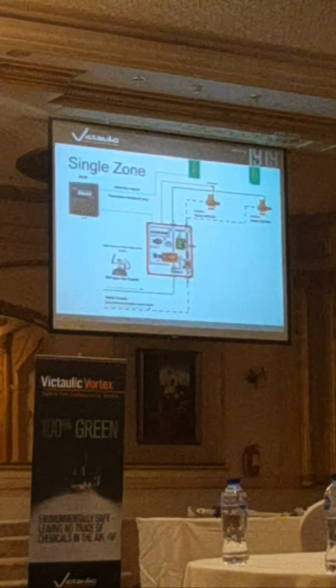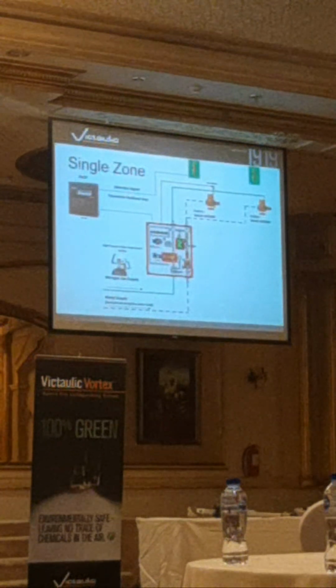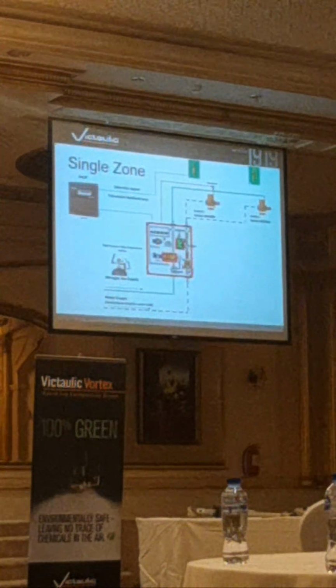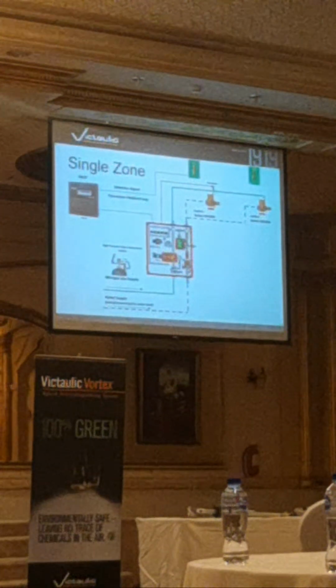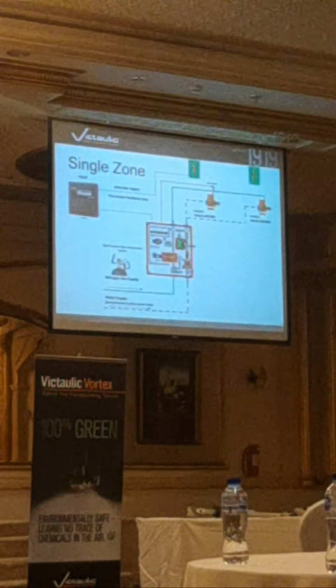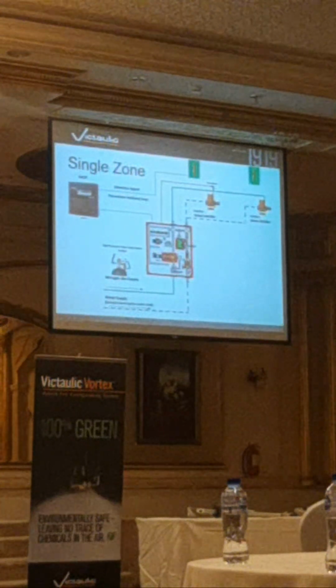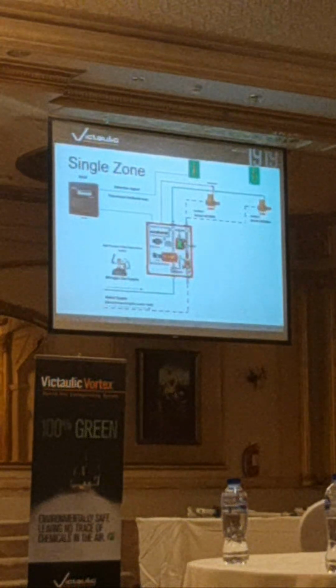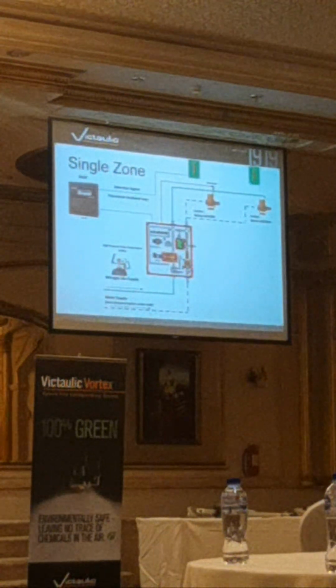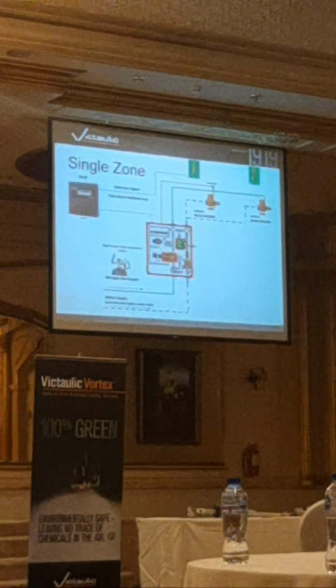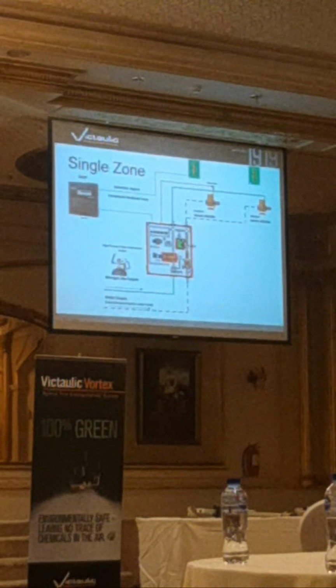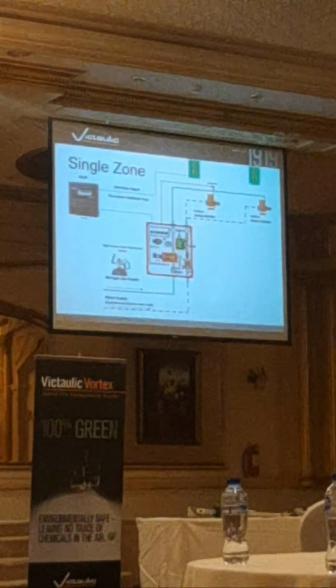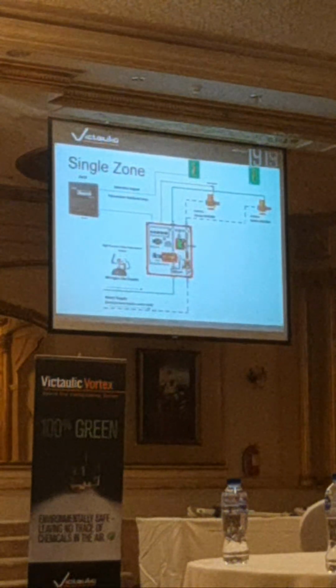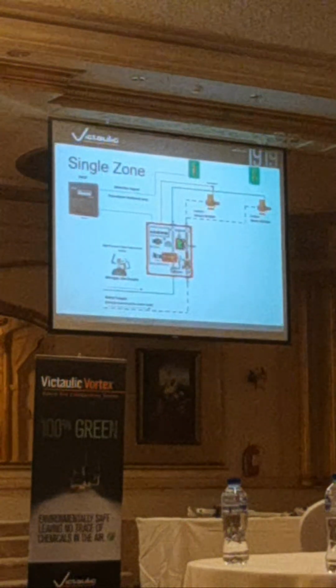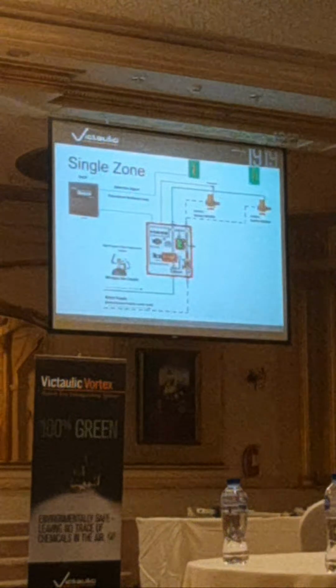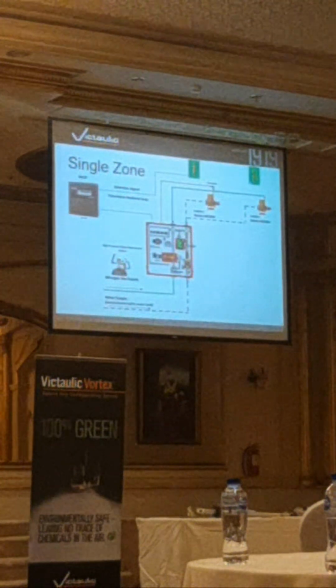Can I have a question? For the water line, the type of the control valve to discharge the water, it's a hydraulic valve, depends on the pressure of the nitrogen line or what? It is the water valve itself, how it is operated? Yes. It is operated with a connection to the nitrogen line. If there's enough pressure of nitrogen, automatically it will open up. If the pressure of nitrogen reduces, the valve will automatically close? Yes, yeah. So it basically has a pressure switch in the nitrogen line. That pressure switch has a set point on both the upside and the downside. And once it is above or below that, it will control that valve. So that's how we control the water.